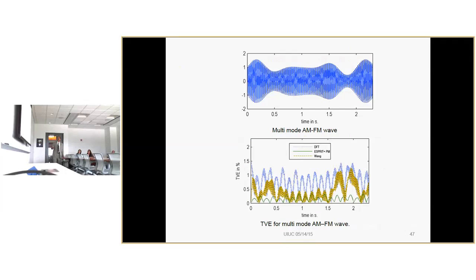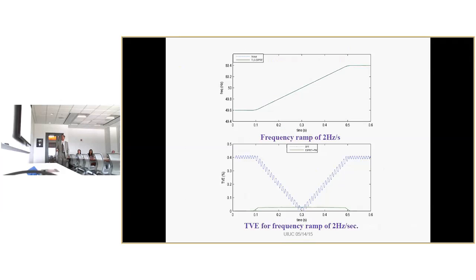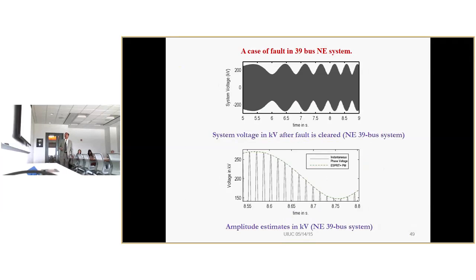This is the multimode case where frequency and amplitude modulations are there. If you see the TVE value, 1% is acceptable. So if you use only DFT, it doesn't meet the requirement. The ESPRIT method, which we have used, is giving less than 0.5%. So it is quite accurate. And then we did a ramp test also, with frequency ramping at this rate. This is the result we got with DFT, which is quite high. And here it is very negligible. The TVE value we got with our method was quite negligible.